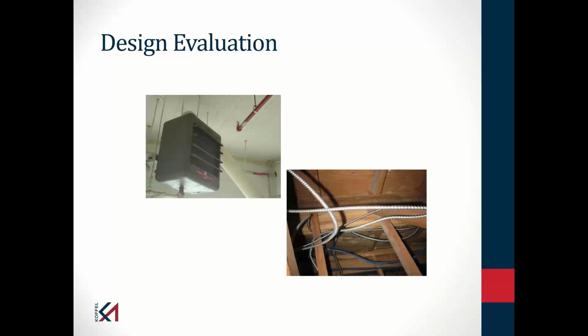Now, the other side of the coin is the cost would be phenomenal if you required a contractor to go in there once a year and reevaluate your system. And that's why I have focused on changes. If we can assume that the system was properly installed initially, then we can really focus on what changes might occur to the building post-initial occupancy that might cause the need for a reevaluation. And on the non-storage side, this can be relatively obvious. I tried to cover a number of them. On the storage side, it's not as obvious.